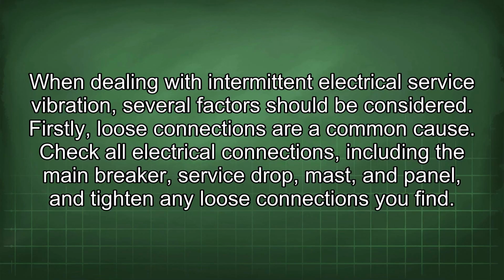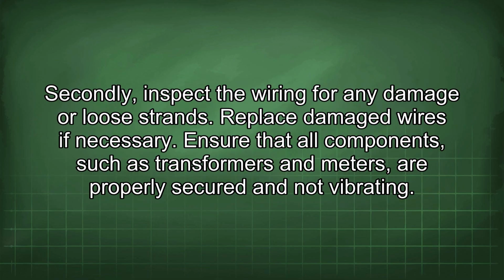When dealing with intermittent electrical service vibration, several factors should be considered. Firstly, loose connections are a common cause. Check all electrical connections, including the main breaker, service drop, mast, and panel, and tighten any loose connections you find. Secondly, inspect the wiring for any damage or loose strands. Replace damaged wires if necessary. Ensure that all components, such as transformers and meters, are properly secured and not vibrating.